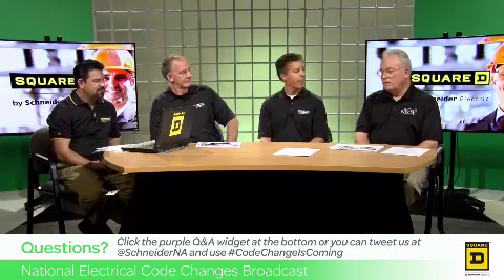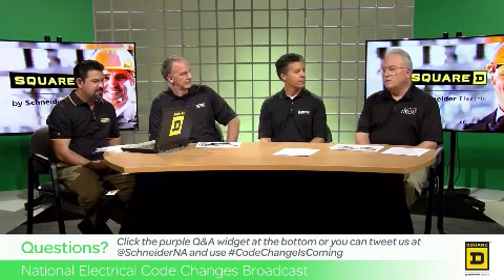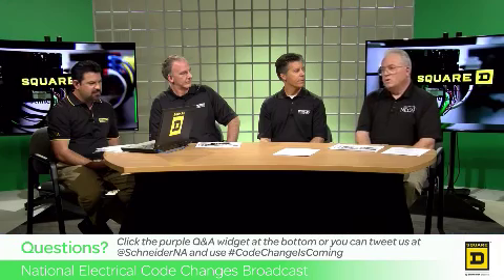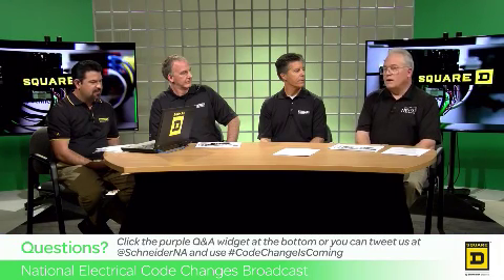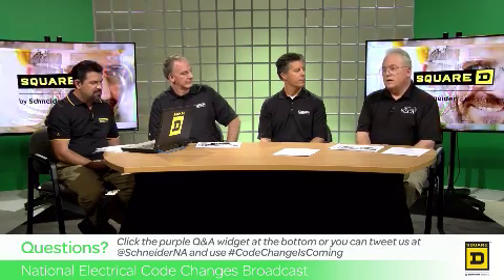And the important thing to remember with this new requirement and the new criteria on the label is that it lines up nicely with use of the table method of establishing incident energy levels and level of PPE to be worn. What we mean by that is you're using a clearing time and an available fault current, and the combination of the two, when you look at the table method in NFPA 70E, is how you arrive at those values for your protection. The difference is that the rules in 70E related to the labels deal more directly with incident energy levels and level of PPE. Panel 1 was very careful not to step over its bounds with regard to what it included on that arc flash warning label, and kept it to installation-related criteria, which is important. NFPA 70 needs to complement NFPA 70E, where everybody wins.